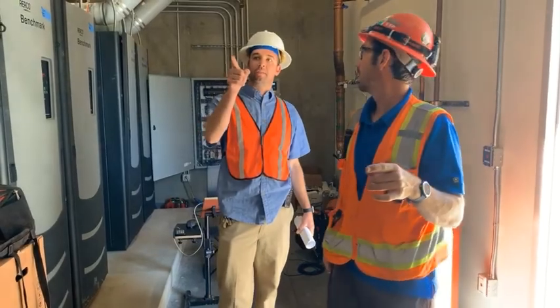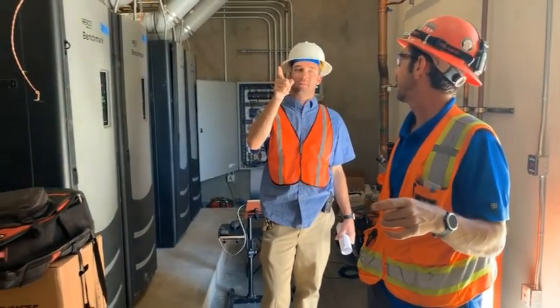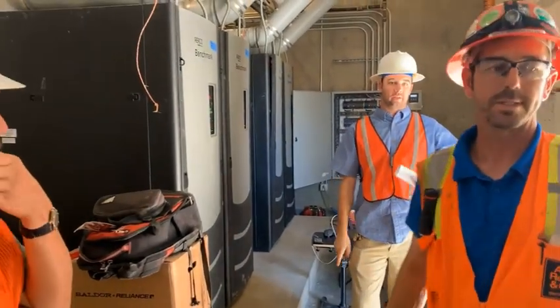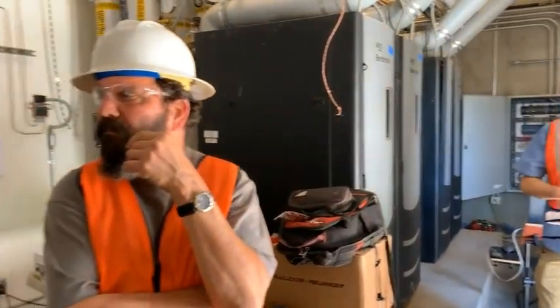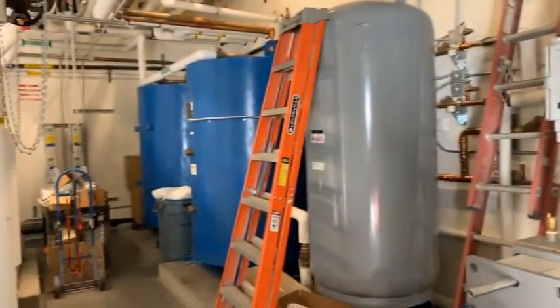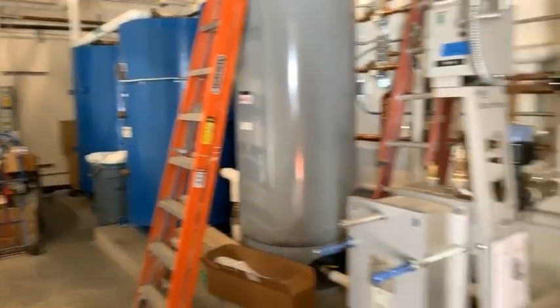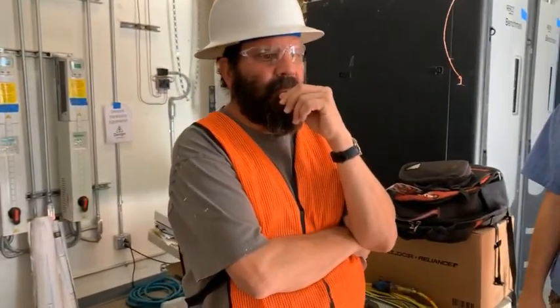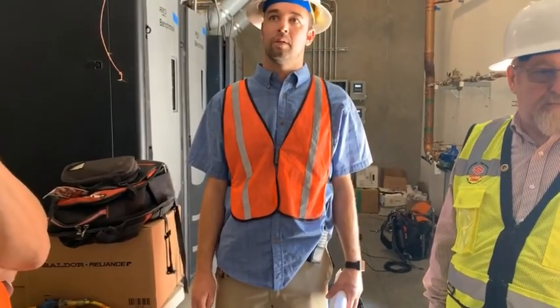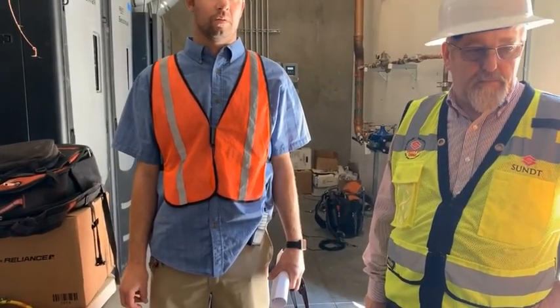Okay. The tanks, do they have check valves on each tank? They don't need check valves on the tanks. Okay. The water can only come out the one way and it won't go back in the other. That's why if you are working on the valve on the tank, you have to shut that tank. Yeah, you have to isolate the outlet valve or isolate all the individual valves. We already took this one apart. That's why I taped it together.